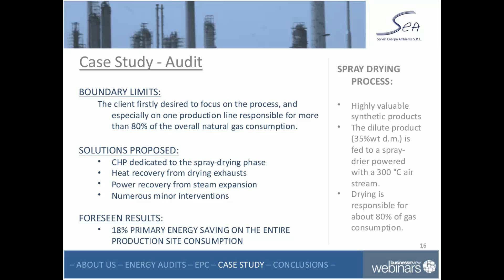So that was the picture regarding energy savings. Now there's another order of issues related to energy, which is power quality. This particular process was very sensitive to power quality. They normally have several shutdowns per year due to poor power quality, mainly caused by very short interruptions, from a few milliseconds up to about 3 seconds. This causes about 35 unintentional shutdowns per year, with significant economic damage at the end of the day. So they were very sensitive to these issues, and they asked us to look into this and find a solution.